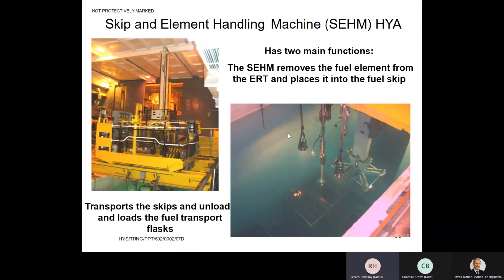So it's just Heysham 1's pond. Like most things at Heysham 1, it's a lot smaller. In fact, it's all boxed in, because one of the original design constraints of Heysham 1 after construction started was something called spalled oxide. They were concerned about getting spalling of oxide from the stainless steel pins, stainless steel undergoing oxidation in the CO2 environment. So they built it, and then they put a big box around it to contain all the spalled oxide, and then found when they ran the reactor that spalled oxide never appeared. So all the spalled oxide modifications were a waste of money. So it's funny, isn't it?